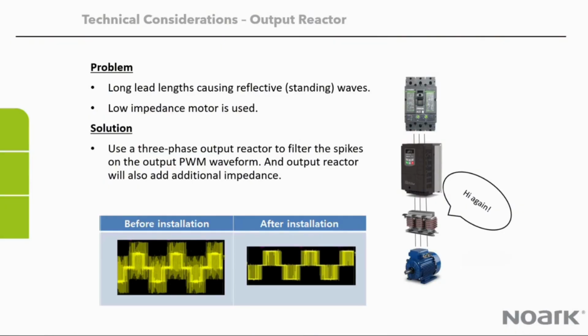When should I use an output reactor? If you've got long lead lengths and you're using a low impedance motor, using an output reactor would help you prevent any potential spikes and add additional impedance for proper operation, a more reliable operation.